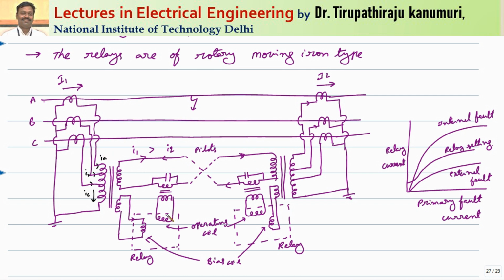Accordingly, this relay will operate at the sending end if the fault is supplied by the sending end. If the fault is supplied from the receiving end also, that means the power transfer can be two-way, or it is fed from both sides, then the current direction of I2 will be reversed. In that case I1 will add to I2, so relay 2 also will trip at the receiving end. That means both the relays, at the sending end and the receiving end, will operate. But if it is a singly fed system, where the fault is fed only from the sending end, then only the relay at the sending end will be disconnected. This is the basic property, and you can see the property is designed like this.